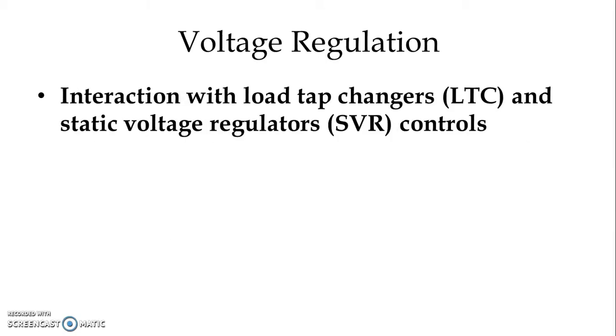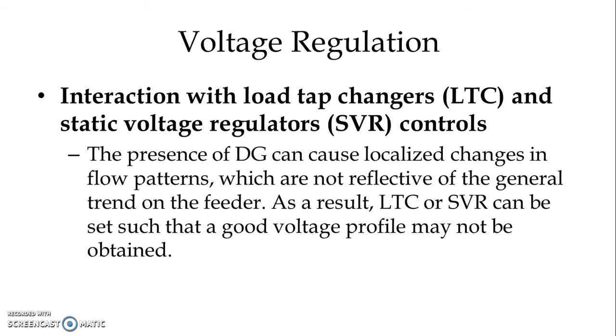Another issue with respect to voltage regulation is in connection with load tap changers and static voltage regulators control. The presence of DG can cause localized changes in flow patterns which are not reflective of the general trend on the feeder. As a result, load tap changers and static voltage regulators can be set such that a good voltage profile may not be obtained.